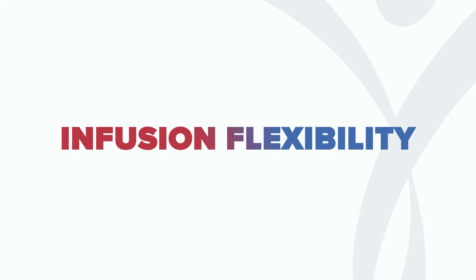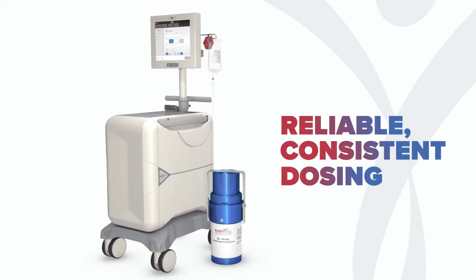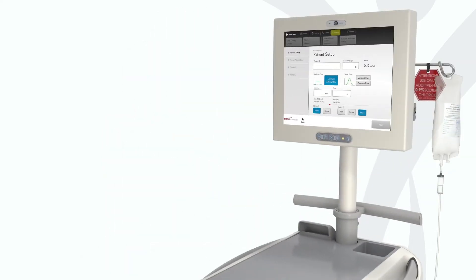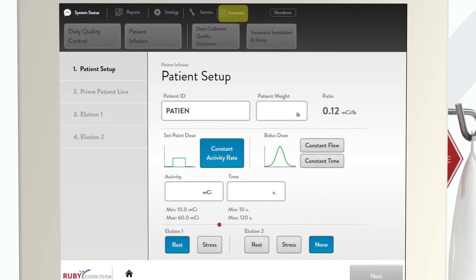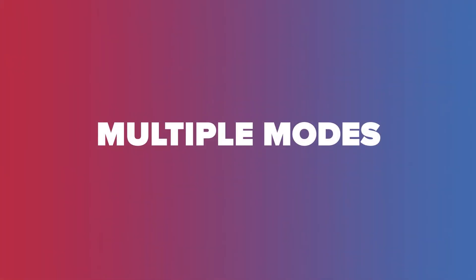Now you can choose unmatched infusion flexibility and reliable, consistent dosing, so that you can have confidence in your diagnosis of patients with coronary artery disease. RubyFill offers personalized weight-based dosing to deliver precise and accurate doses of rubidium to your patients. It is automated — simply enter the patient's weight, and the system calculates the dose for you. It also offers a choice of elution modes so you can select how you'd like to administer the dose.